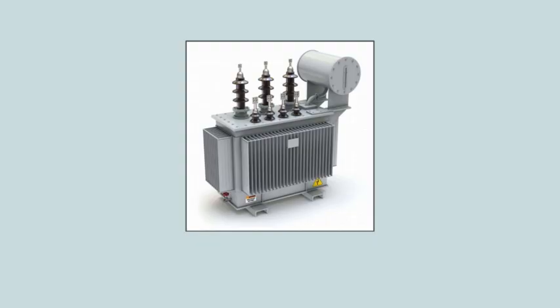There are different sizes of transformers. A 25 kVA transformer would feed approximately 10 homes, and a 300 kVA transformer could reasonably serve between 50 and 150 homes depending on local conditions and population density.